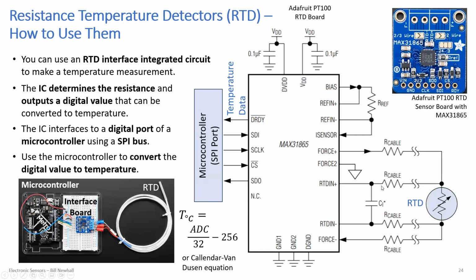You have very little current going through those two inner connections, because RTD in is probably a very high impedance input. So you get a negligible or zero voltage drop across those two sense cables since there's no current through them. There's also a capacitor here, which is there as a filter.